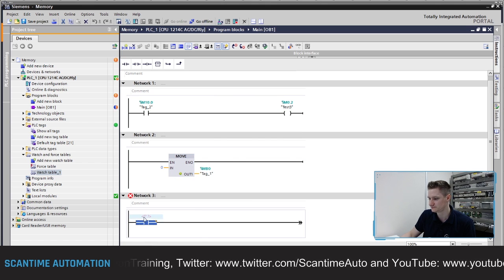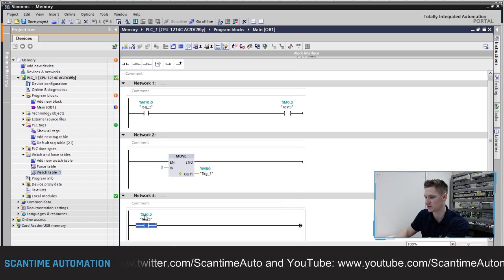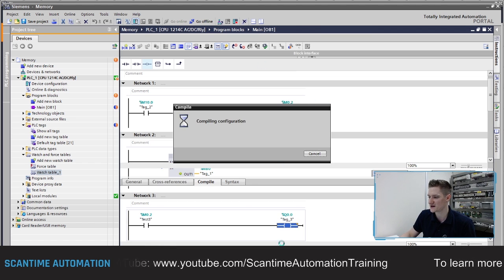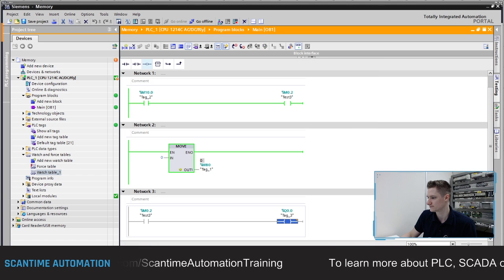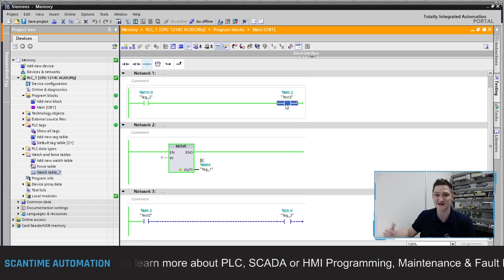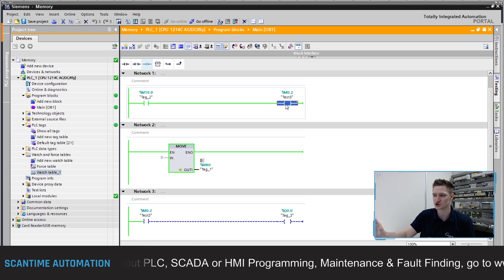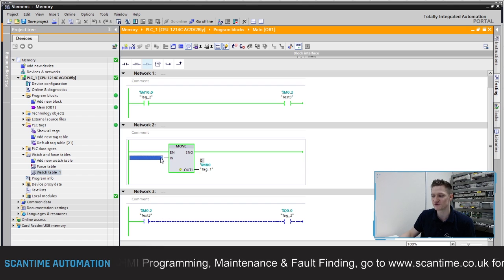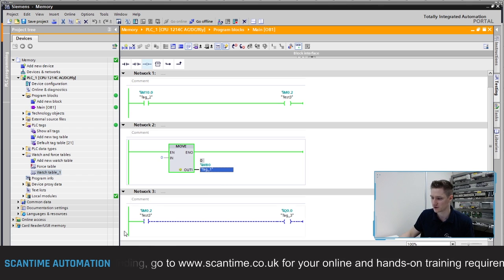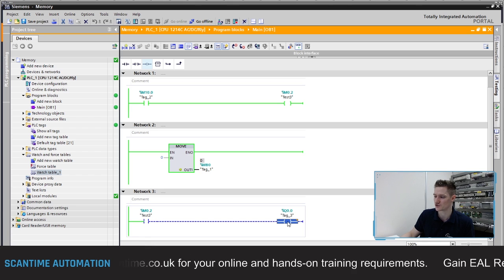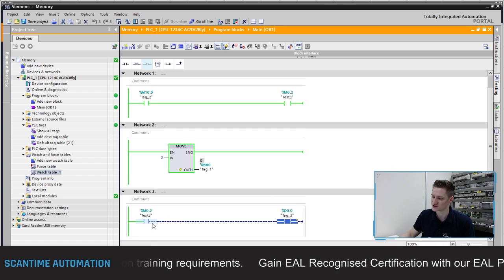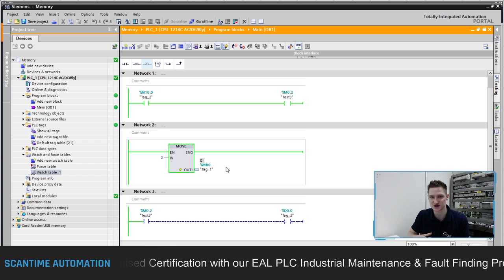If I go into the program and in network 3 type in M0.2 turning on a coil for Q0.0, when I download to the PLC that coil will be off. And there it is. M10.0 is on, M0.2 appears on at this point in the program so the laptop updates and displays as though it was on, but then we move zero into MB0 and zero out that register - all bits in that byte turn off, M0.2 is now off, and that is turning off Q0.0. That there is a conflict in the addressing.